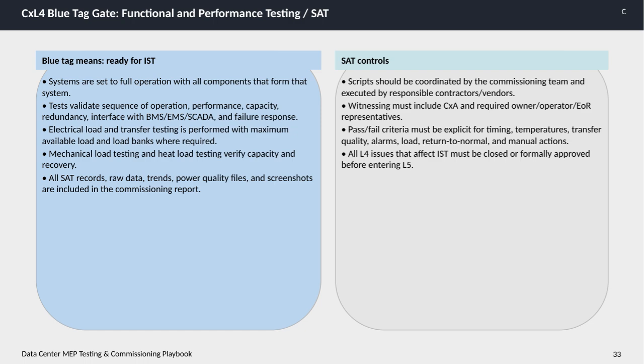The testing process is tightly controlled. Scripts for testing should be coordinated by the commissioning team and carried out by the responsible contractors or vendors. Witnessing of these tests isn't just a formality. It requires the presence of the commissioning authority, as well as relevant owner, operator, and engineer of record representatives. Clear pass or fail criteria must be set ahead of time, covering key factors like timing, temperatures, transfer quality, alarms, load conditions, and manual operations. Lastly, any Level 4 issues that might impact integrated system testing must either be fully resolved or formally approved before moving forward to Level 5. This ensures a smooth transition and a robust, reliable system.